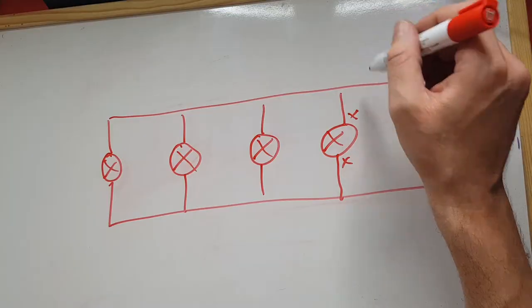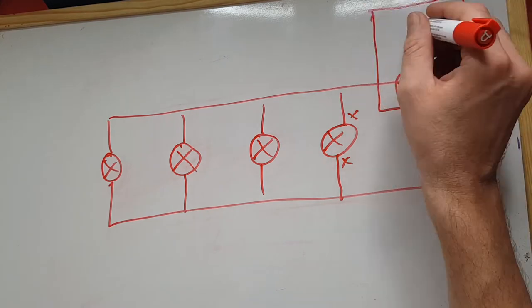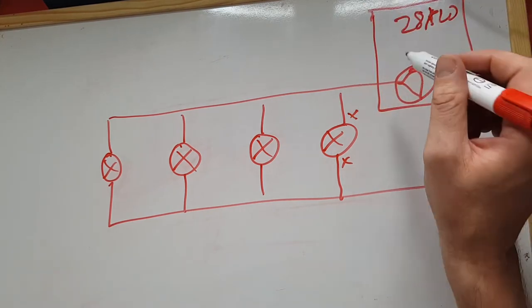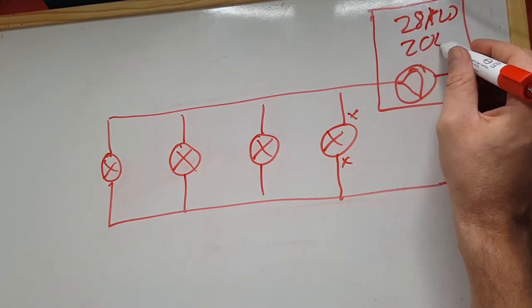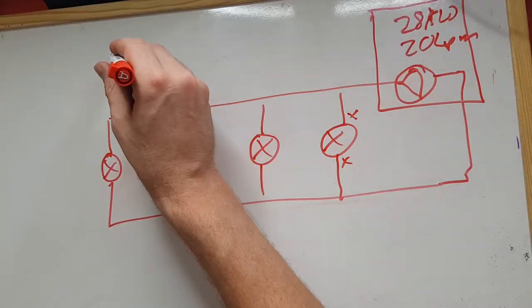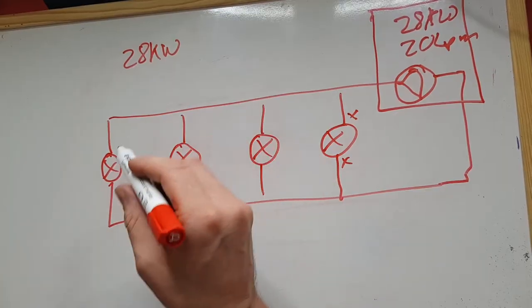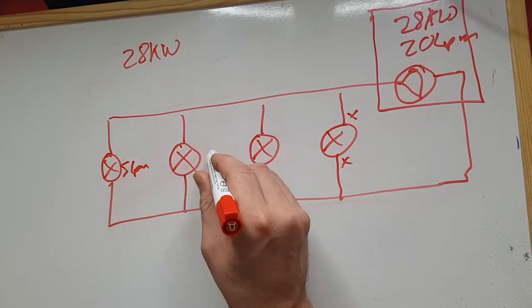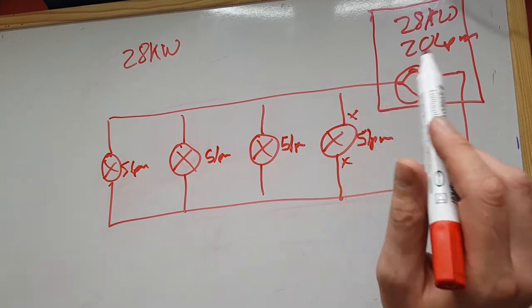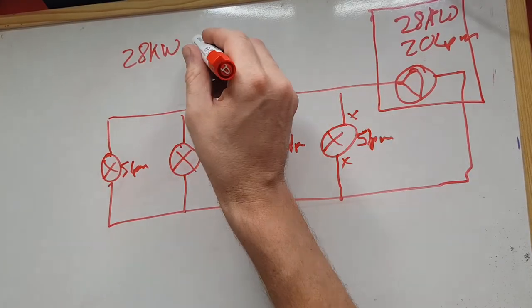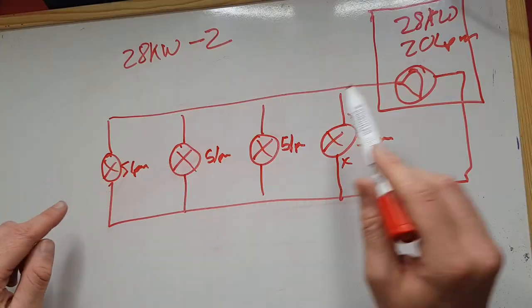So let's take an example of 28kW again, because it's simple maths. If we said this pump was in a 28kW boiler, it would require 20 litres a minute to maintain delta T20, and that's what it's going to output. Let's say the load is also 28kW, and each of these zones is 7kW. So 7kW is going to need 5 litres a minute. This 28kW load is when it's minus 2 outside, so 4 times 5 is 20 litres a minute — this will work.